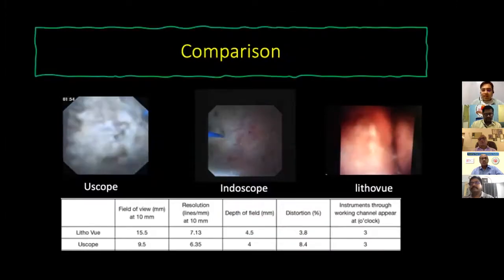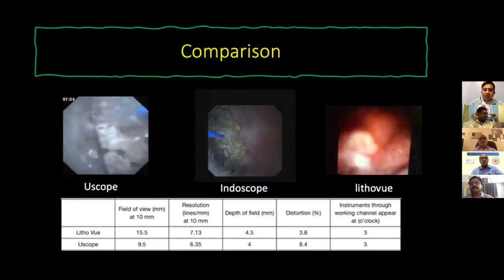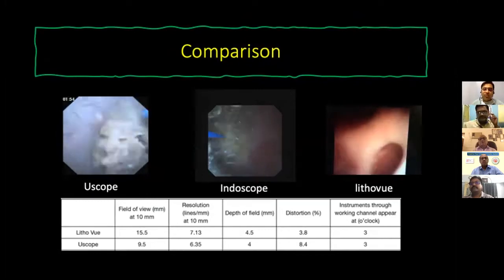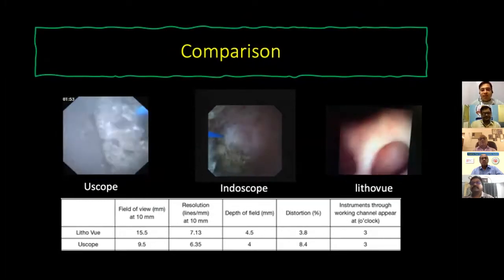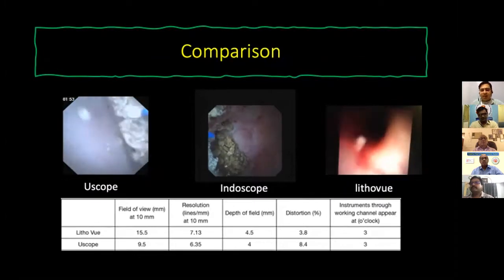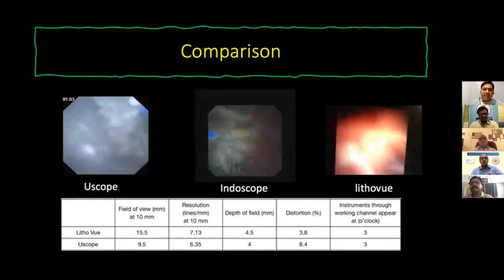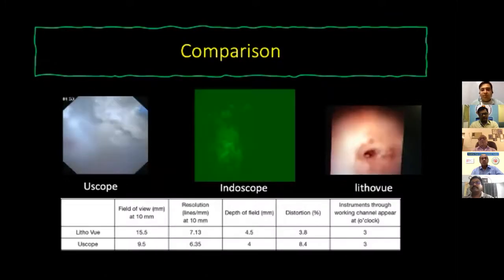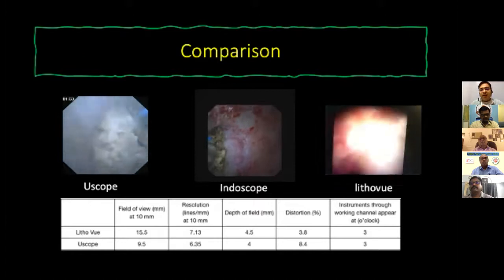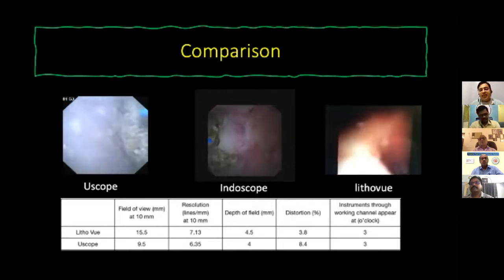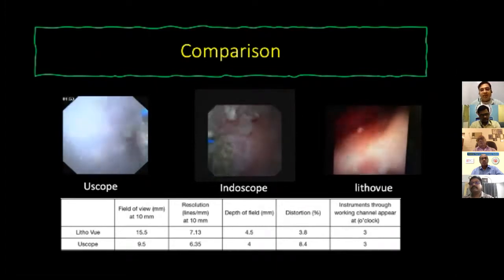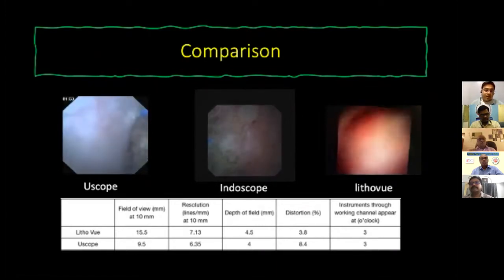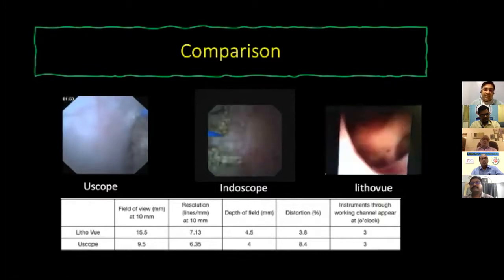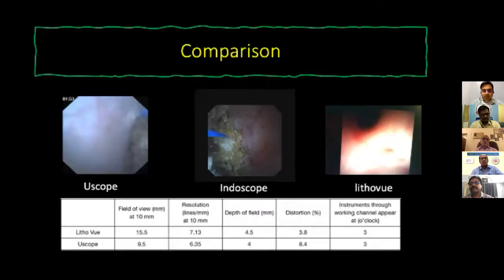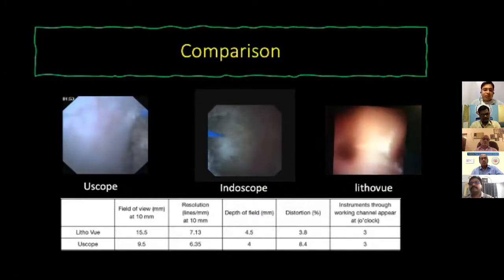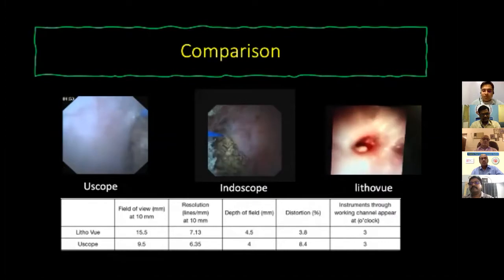So when you compare the vision of the Uscope, Indoscope, and LithoVue, because these are the three proprietary things, definitely it is comparable, though without objective analysis, it is improper to say that one scope has better vision than the other. But definitely it is, to say the least, comparable, and the color enhancement, I would say, is slightly on a better side as compared to the Uscope, though obviously without any objective analysis, it is improper to make a comment. It has a field of view of about 110 degrees, and the depth ranges about 2 to 50 mm.